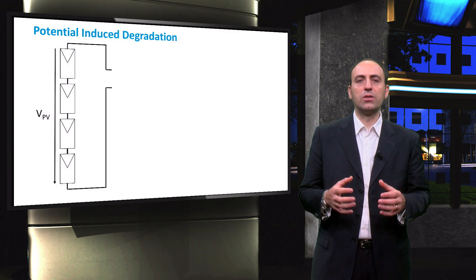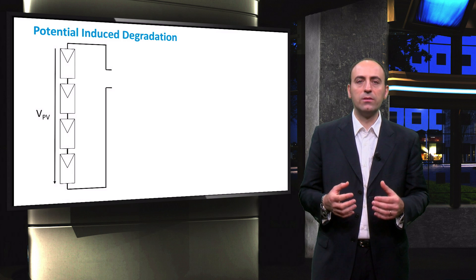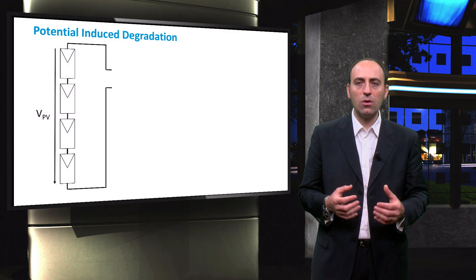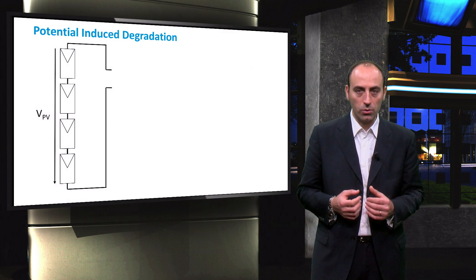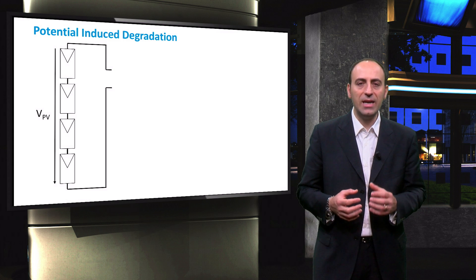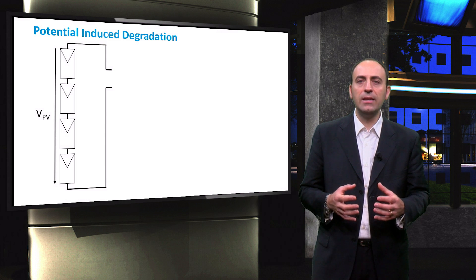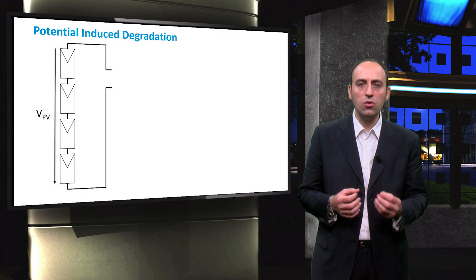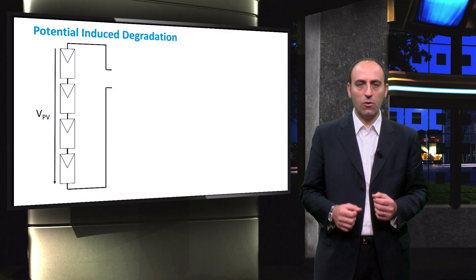Potential induced degradation is a phenomenon that occurs when the voltage on the module and the leakage current act as a driver of ions within the module. The PV system and the environment interact to cause PID. This is due mainly to the fact that humidity and dust on the panels can cause sodium ions to affect the performance.